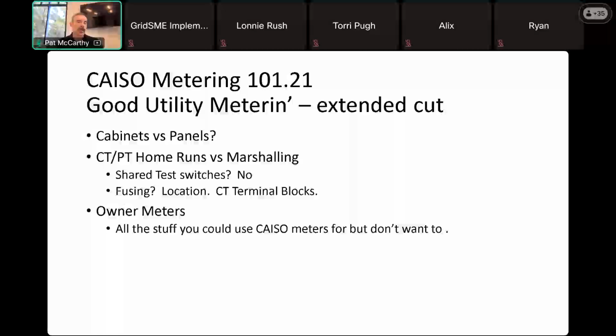You can put meters in cabinets, inside or outside, with a lock on them. You can put them in a relay panel, open back, just like any other device in a substation. With respect to your metering current and voltage transformers, you can do a home run - a single piece of wire from the terminal of the transformer all the way into the first test switch block of the meter. Or you can, as protection and control folks like to do, land in a marshalling cabinet and use your cable tray up top. The first two bullets are pretty well related from a metering perspective, and that's the nuance of the game.